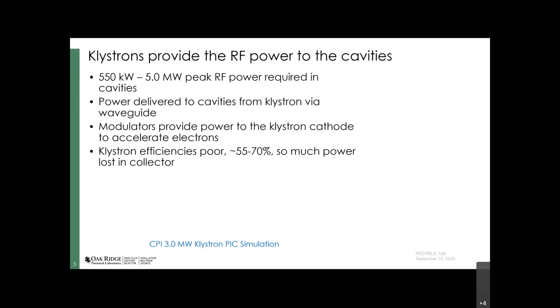The modulators then in turn are used to power those klystrons. And the klystron efficiencies are rather poor, so a lot of the power is lost in heating of water. So this is kind of a little schematic of what a klystron looks like. If you see down at the base, what we have down here is what's called a cathode, or an electron gun. We heat this up. The electrons are available to be accelerated once you apply an electric field across an anode and cathode. All this is, of course, in vacuum. That electron beam is then accelerated up vertically, in this case, towards the end of the device. Because it's all electrons, space charge tends to cause the particles to want to repel. So there's a solenoid field that retains that and focuses that.